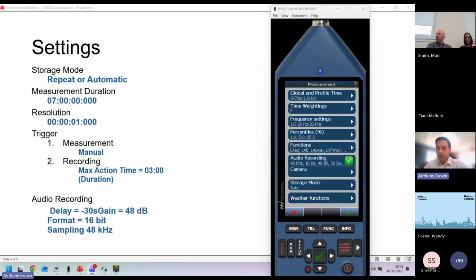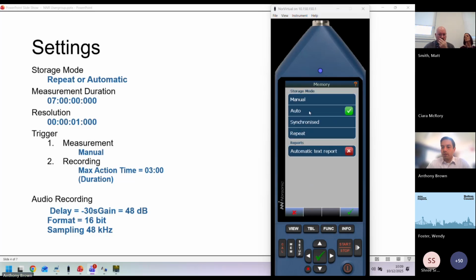Let's have a look at the next part underneath the audio recording. We're in the measurement screen. We've completed the audio recording settings, and now we've got the storage mode. In storage mode, you can set the meter to how it should run. We normally set this to automatic, meaning when you press the start button, it will run for 7 days, then stop and save the measurement at the end of the 7 days.